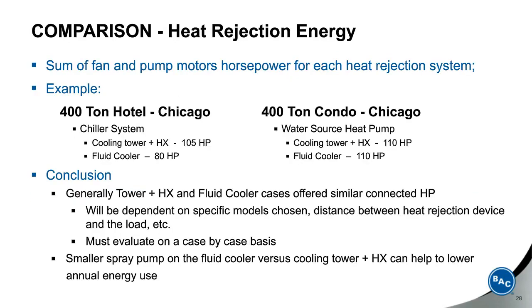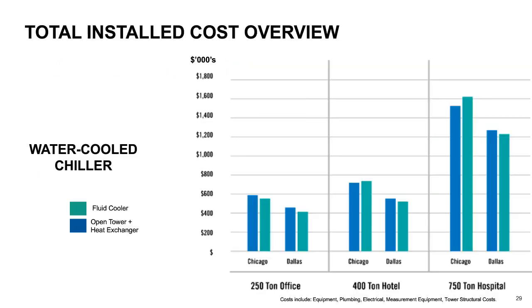So the first aspect that was looked at was the comparative energy usage across two buildings with equivalent load requirements in Chicago, one using a chiller system and one using a water source heat pump. Generally, the connected horsepower usage was similar. In the two examples cited here, it was a match in the condo, and the fluid cooler used a little less in the hotel environment. But as I mentioned earlier, it must be remembered that each examination is a unique case dependent on the specific model applied, the exact layout, and a host of other variables, and each project must be individually evaluated. So I'm going to hand back over to Frank.